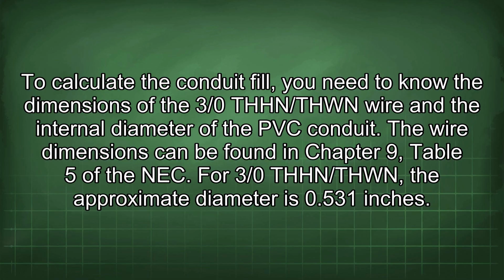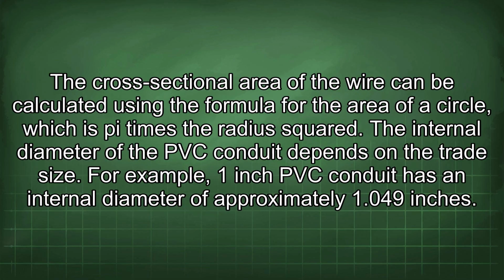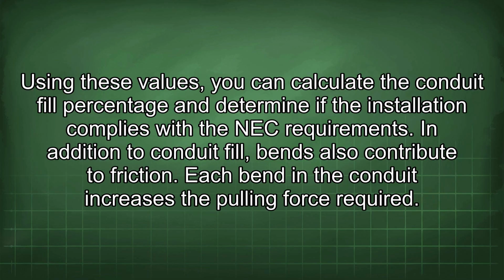For 3/0 THHN/THWN, the approximate diameter is 0.531 inches. The cross-sectional area of the wire can be calculated using the formula for the area of a circle, which is pi times the radius squared. The internal diameter of the PVC conduit depends on the trade size. For example, 1-inch PVC conduit has an internal diameter of approximately 1.049 inches. Using these values, you can calculate the conduit fill percentage and determine if the installation complies with the NEC requirements.